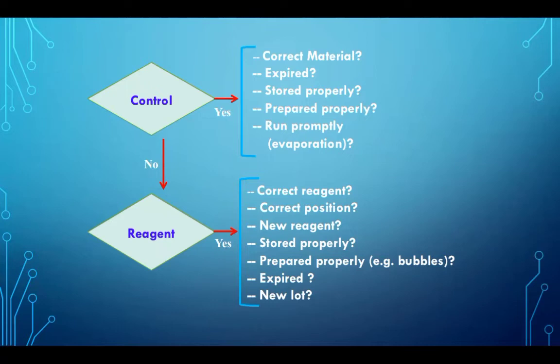If it is a new reagent, lot acceptance testing has been performed. New lot, you have performed lot acceptance and it was okay. It is stored properly under defined conditions. If it needs to be reconstituted, it is reconstituted properly.